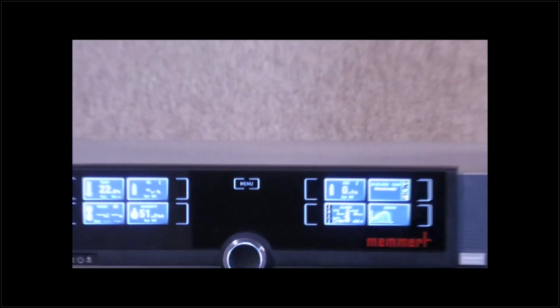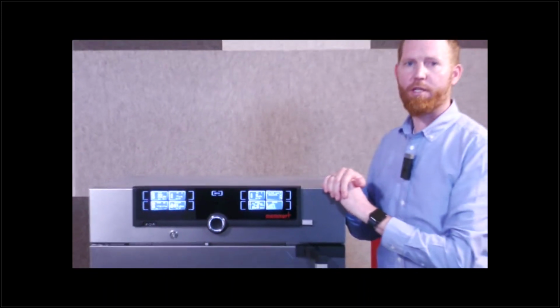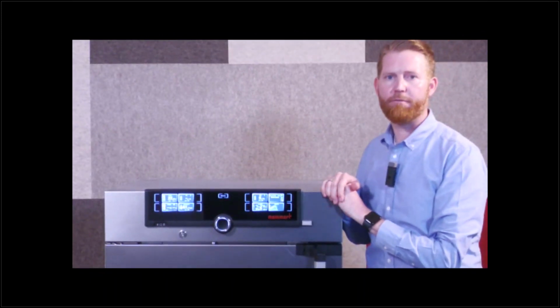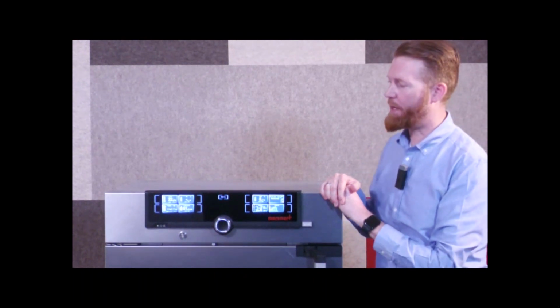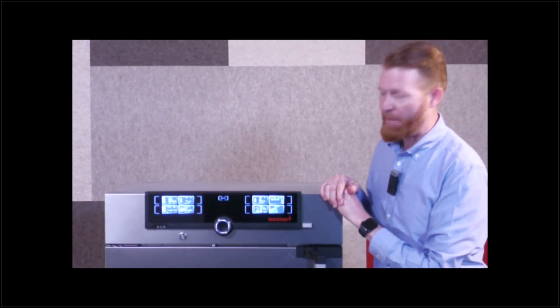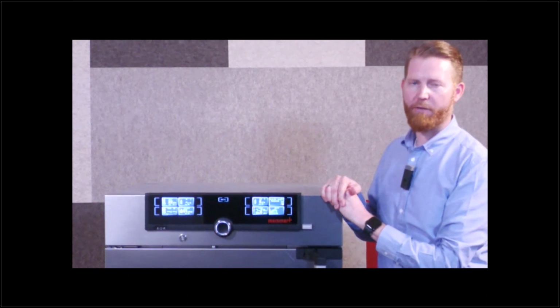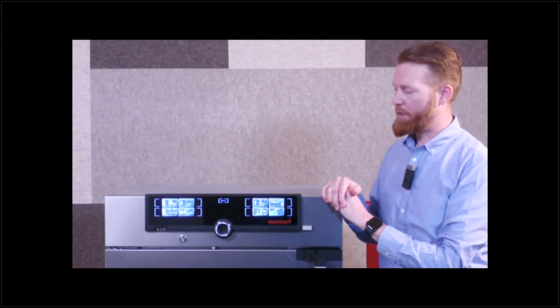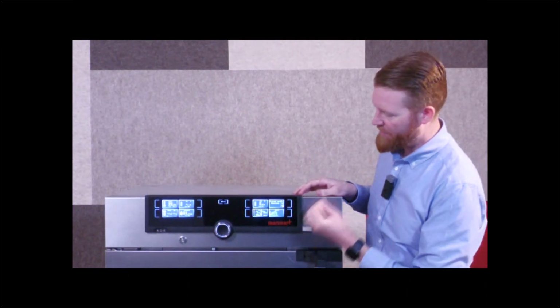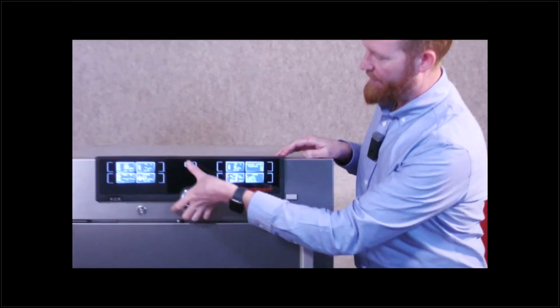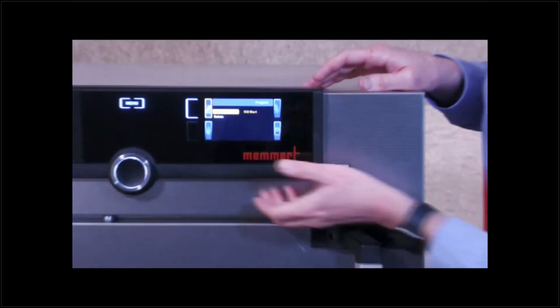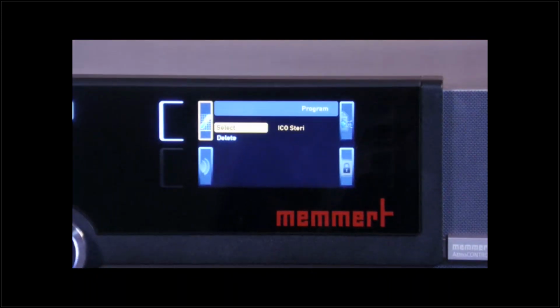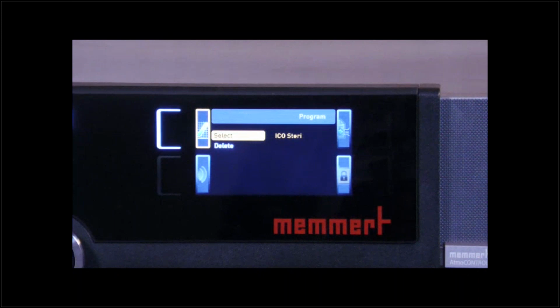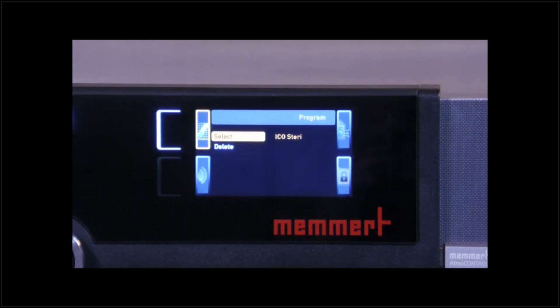We talked about sterilization. Sterilization is an important factor when working in the biopharma lab. I mentioned already that many CO2 incubators are equipped with a sterilization routine directly on the controller. In that case, we have also installed a so-called sterilization program, which can be chosen directly here. For this machine, it is a 180-degree sterilization for 2 hours.